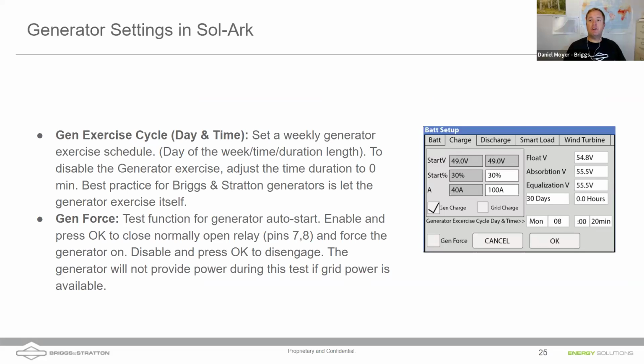Great, thank you. A couple other options you may have noticed on the charge tab is the gen exercise. You can program the Sol-Ark to automatically start up the generator and exercise the generator. This can be adjusted. I would recommend, at least for the Briggs & Stratton products, that the ability to exercise itself can be handled by the generator itself, and we can adjust that. I would always recommend not adjusting the date, because inevitably you're going to get homeowners who call you and say, why is my generator running? By default, they're all April Fool's Day, and I believe later in October as well. So you don't get those calls. If you start getting one or two calls, you figure out what's happening and you can let them know. So I would leave it up to the generator.